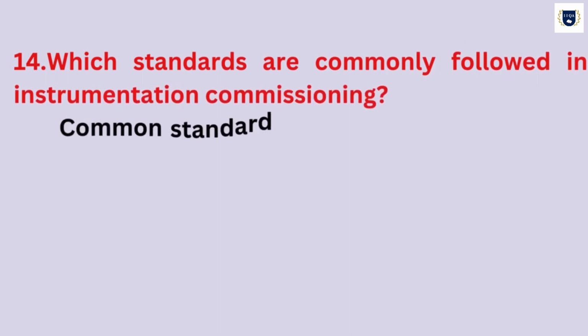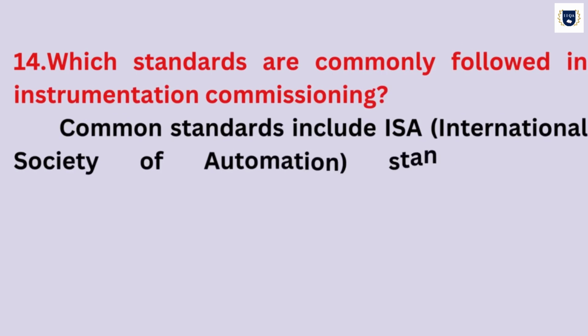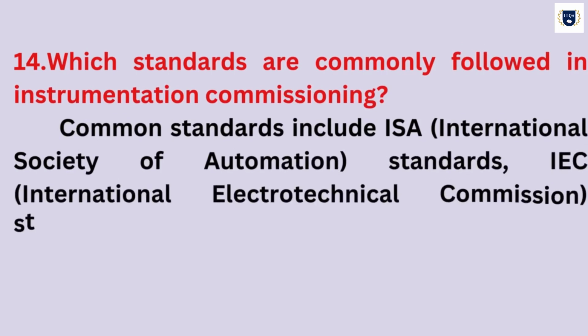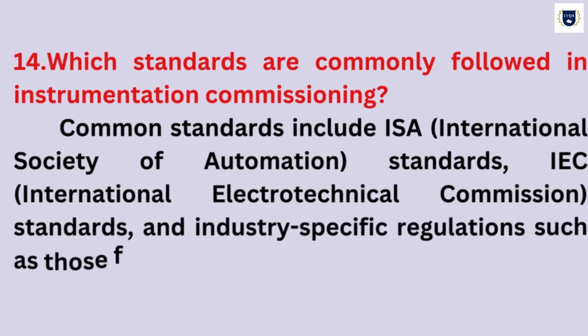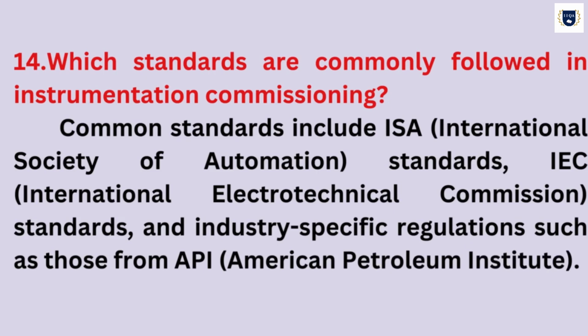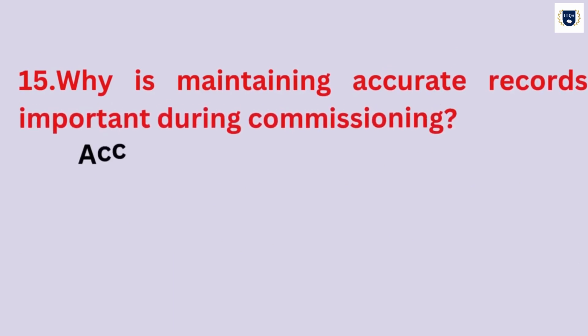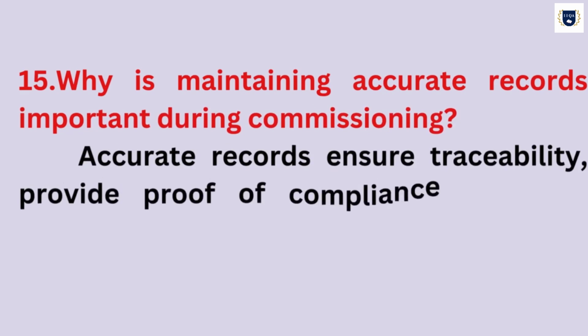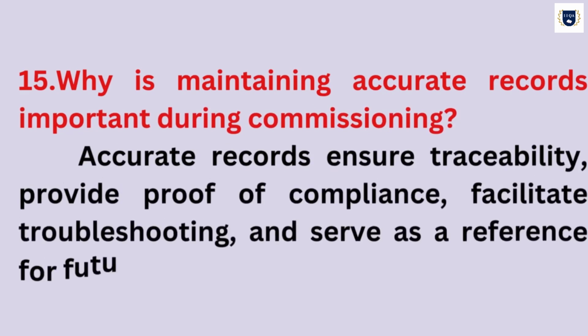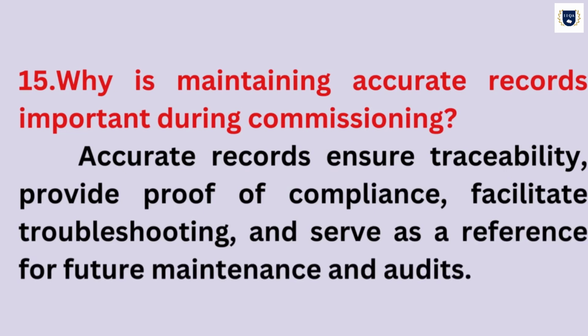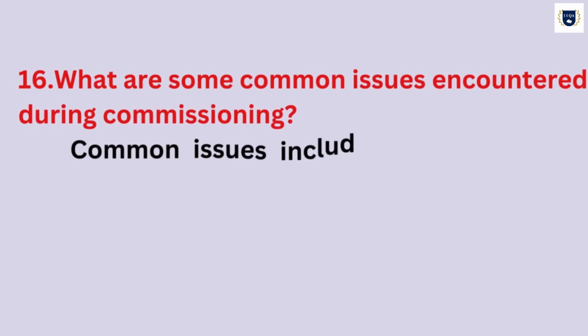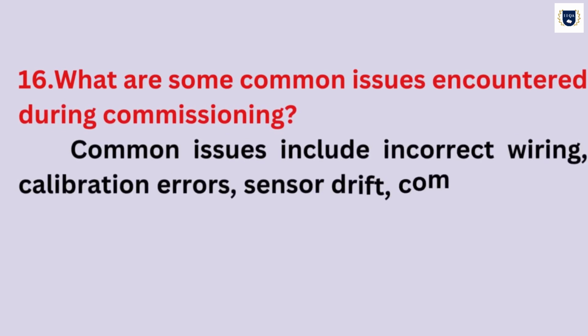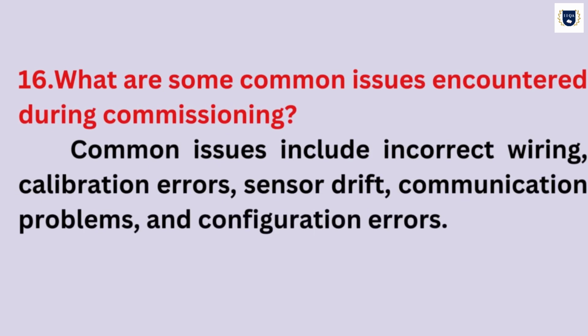Which standards are commonly followed in instrumentation commissioning? Common standards include ISA, International Society of Automation, standards, IEC, International Electrotechnical Commission, standards, and industry-specific regulations such as those from API, American Petroleum Institute. Why is maintaining accurate records important during commissioning? Accurate records ensure traceability, provide proof of compliance, facilitate troubleshooting, and serve as a reference for future maintenance and audits. What are some common issues encountered during commissioning? Common issues include incorrect wiring, calibration errors, sensor drift, communication problems, and configuration errors.